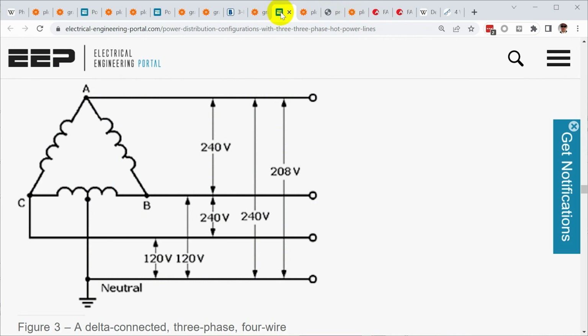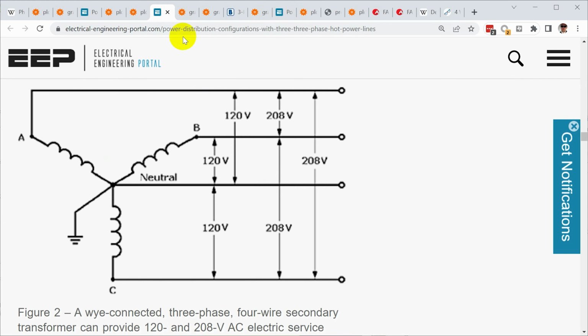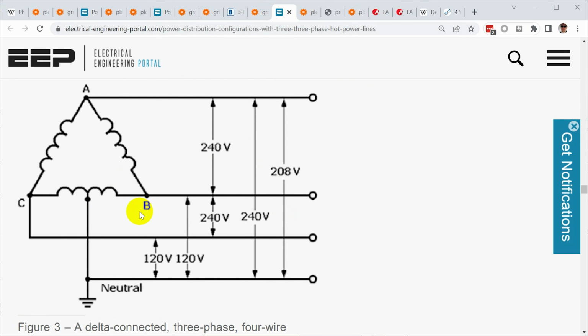The thing you have to understand, though, is that this is not centered around the neutral. The neutral is instead referenced to the center tap of one of the phases, as opposed to, as in a Y configuration, being the center of the three phases. So this is where all the confusion comes from. People are expecting a Y configuration, and the output of this thing is not a Y configuration. It's a high leg delta.